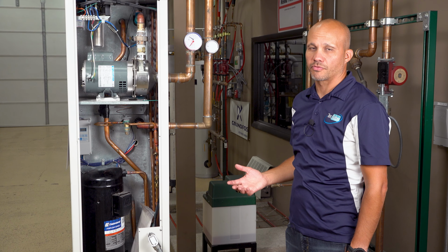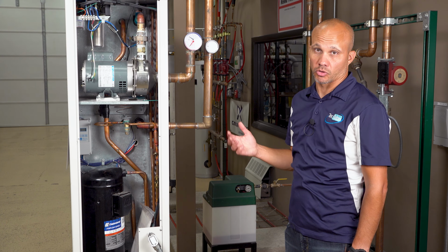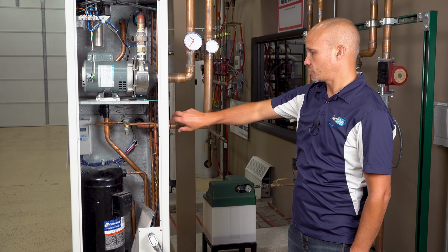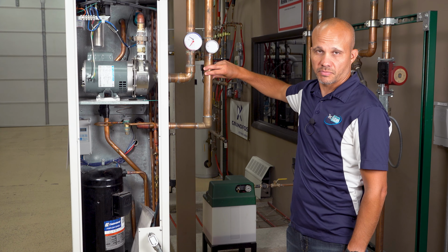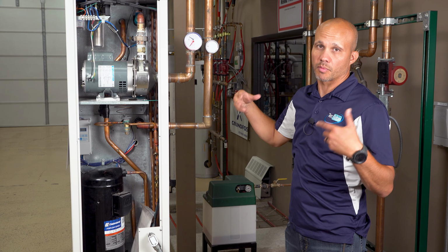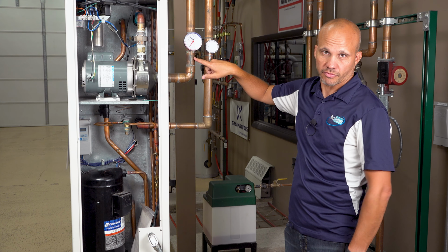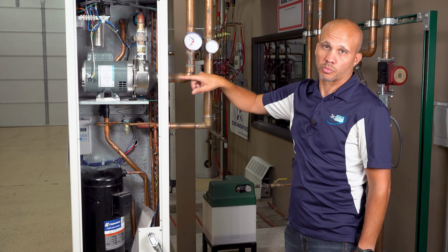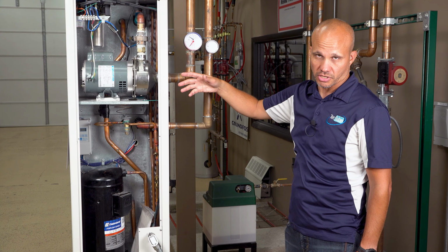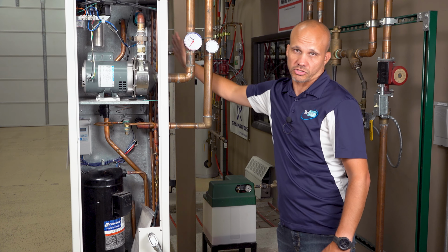Our last example for you today is a heat pump chiller. Now, a chiller in general makes cold water, hence the name chiller. So it sends cold water out on the piping system. That cold water goes through all types of indoor coils where they can absorb heat from the building, and then it brings back slightly warmer water with all that heat from the building back into the chiller, where the chiller can do our regular refrigeration cycle, compress the gas and all of that, and reject the heat to the coils on this unit.